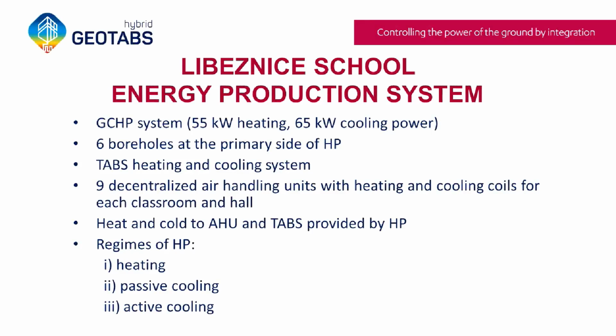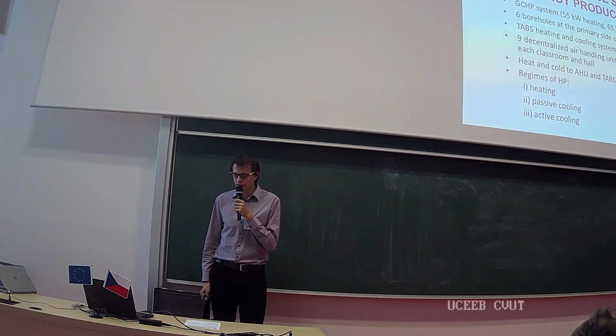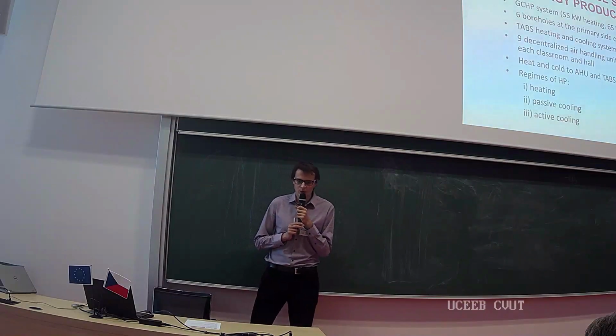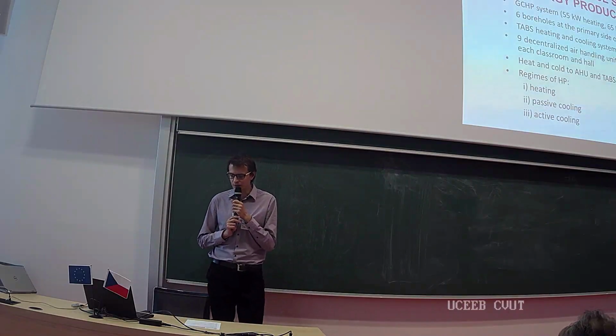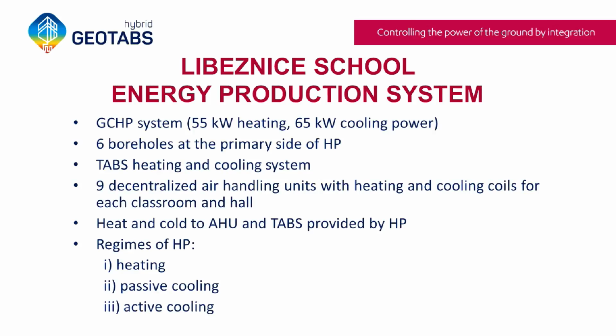So now I will talk about the energy production system of the building. As I said, it's a ground-coupled heat pump system. The heat pump can provide 55 kilowatts in heat and 65 kilowatts in cold. The bore field has 6 boreholes, which are 130 meters deep. There is a TABS system for heating and cooling, and also 9 decentralized air handling units for each classroom and the multifunctional hall. The air handling units have also heating and cooling coils. And the heat and cold for the air handling units and for TABS is provided by the heat pump.